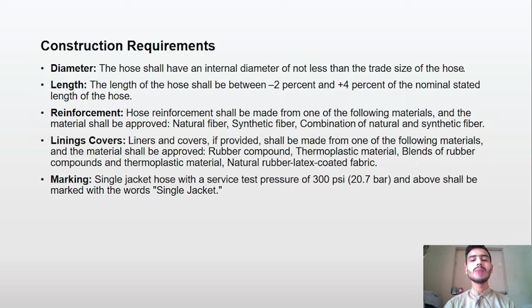Reinforcement shall be made from one of the following materials: natural fiber, synthetic fiber, or a combination of natural and synthetic both. Number four is linings and covers. Linings and covers, if provided, shall be made from one of the following materials and materials shall be approved. What are those materials? Those materials are rubber compounds, thermoplastic material, blends of rubber compounds and thermoplastic materials, natural rubber latex coated fabric. The last one is marking. Marking: single jacket hose with a service test pressure of 300 psi or equivalent to 20.7 bar and above shall be marked with the words single jacket.